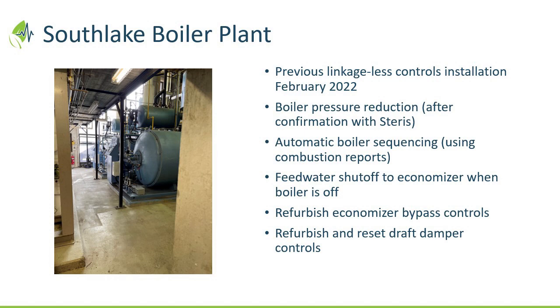Now, in reality, that's next to impossible to do because there's so many factors that play into that. But what linkageless controls allows for, and this technology has been around for 20 plus years now or more, it just allows you to meter the gas and the air specifically across the entire combustion curve. So traditionally, you would look at, say, fuel input, and you would measure an approximation of air across your firing range. Well, linkageless allows you to set up all the way across that curve. So as we get into things like the draft, for example, as you become really, really well-tuned in that combustion process, think of like a race car, for example, everything else becomes important. Pressure becomes important, air density plays a factor, draft becomes very, very important. So everything that goes in has to be very well measured, very well controlled.